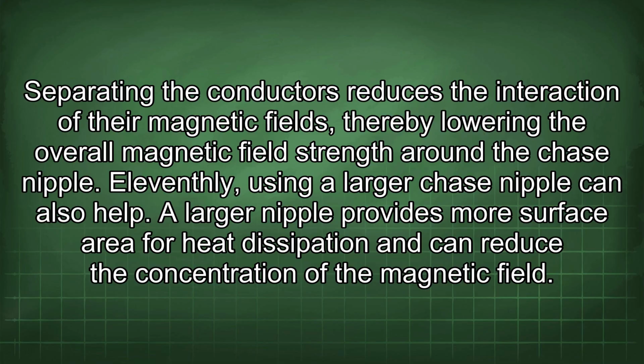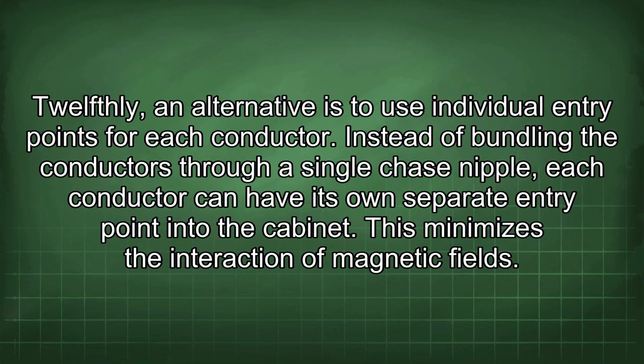A larger nipple provides more surface area for heat dissipation and can reduce the concentration of the magnetic field. Twelfthly, an alternative is to use individual entry points for each conductor. Instead of bundling the conductors through a single chase nipple, each conductor can have its own separate entry point into the cabinet. This minimizes the interaction of magnetic fields.